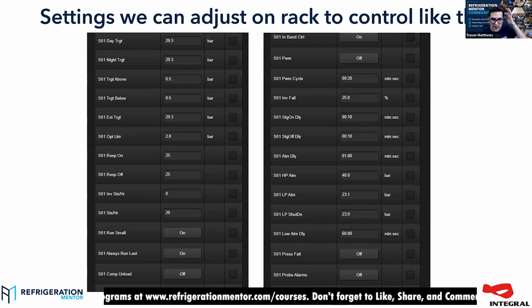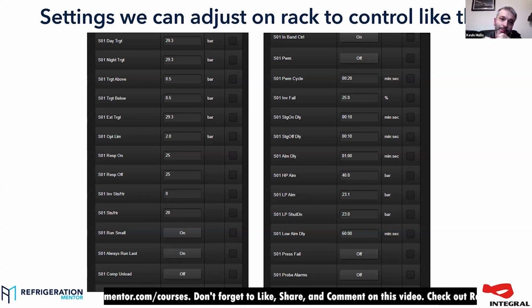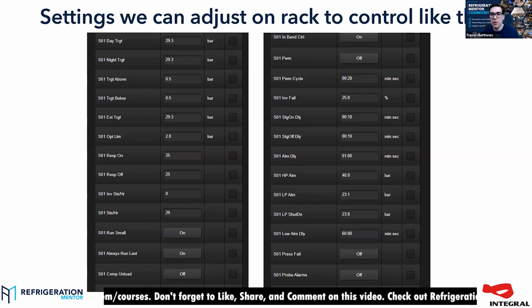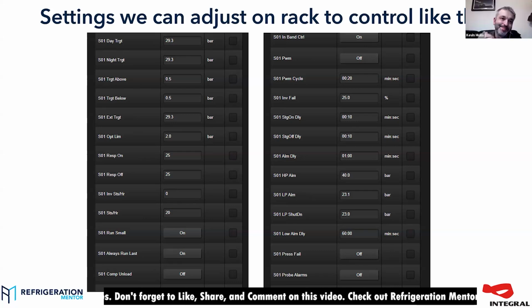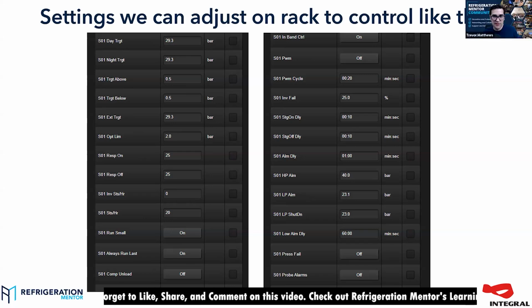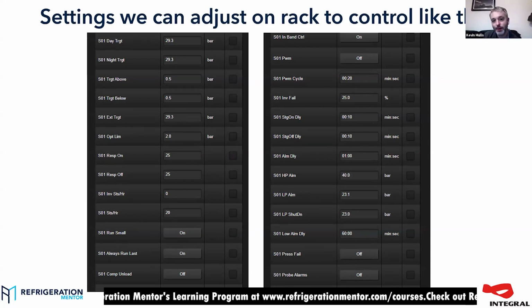And I'm seeing this in big commercial CO2 systems. So now we've got big cold storage, and the biggest problem, even in supermarkets, it doesn't matter. One of the problems I see is, okay, we're expanding in 2 years, so let's get this big rack for all this load. And I was at one yesterday where one compressor turns on, it runs for a couple of minutes, and then it shuts off. The whole thing is sadly just over capacity. And they're like, we've got to put another drive on this one, or change the setting, because now it's so cold out that the gas cooler coil is frozen solid.